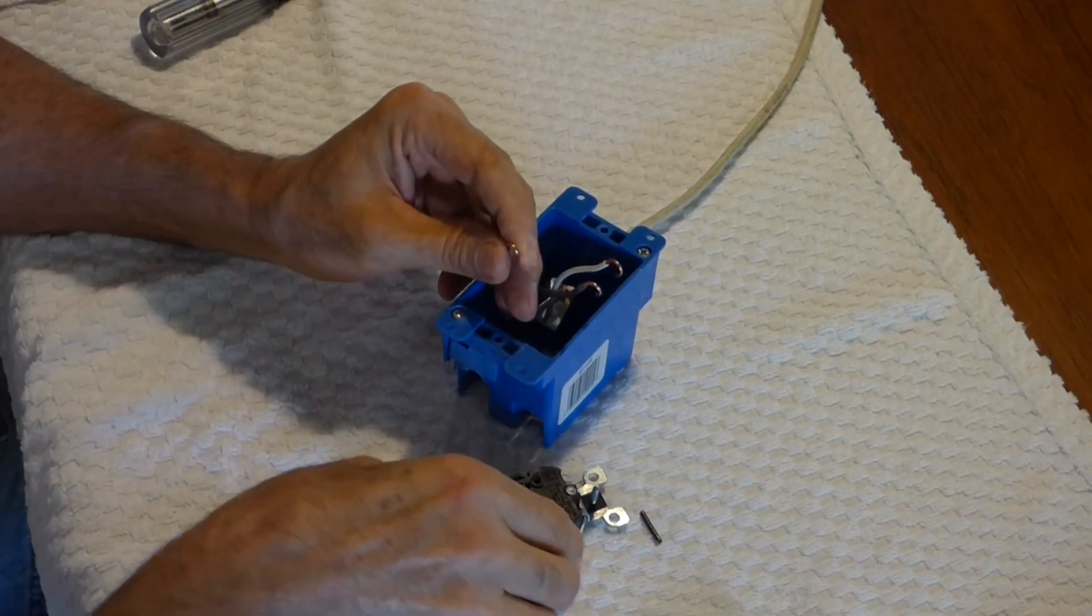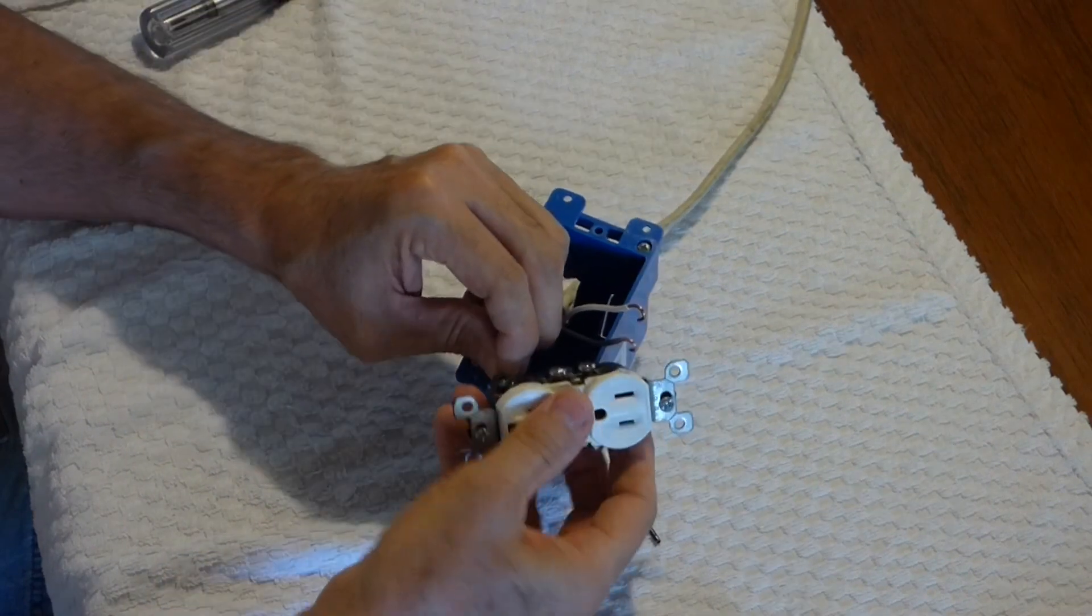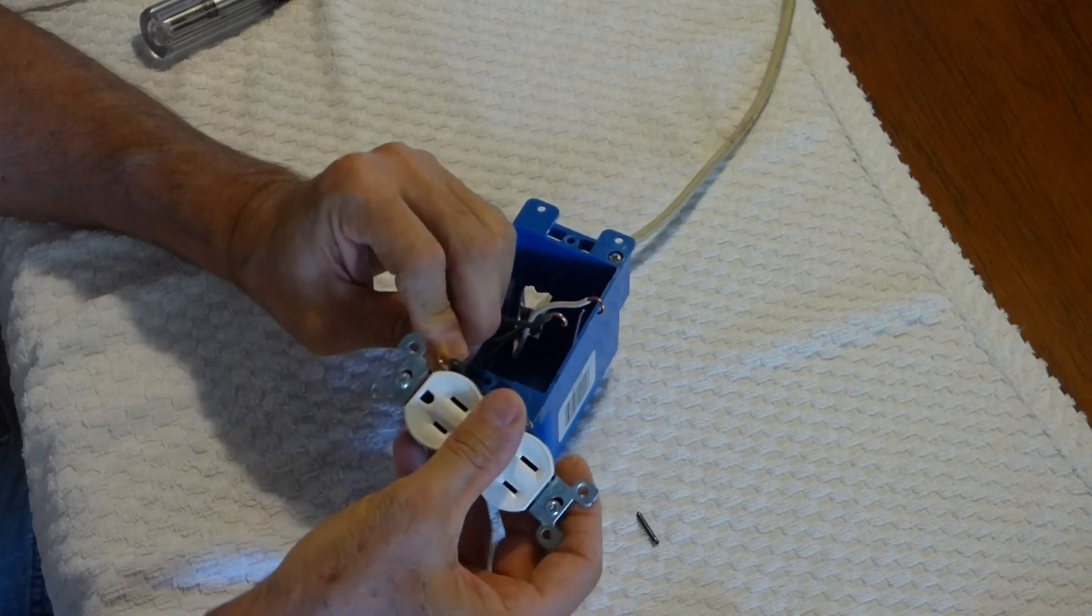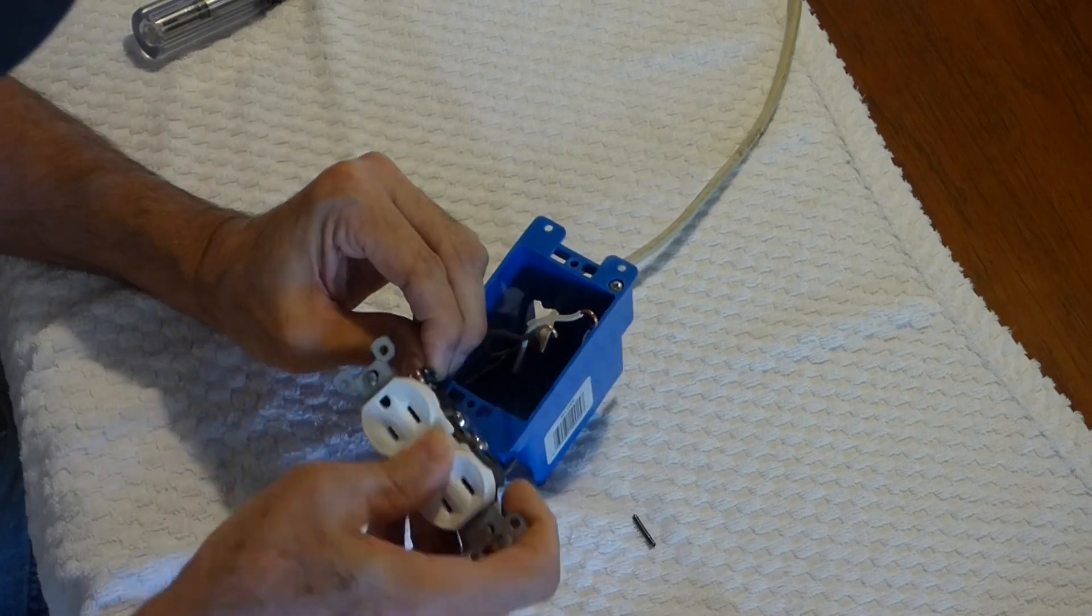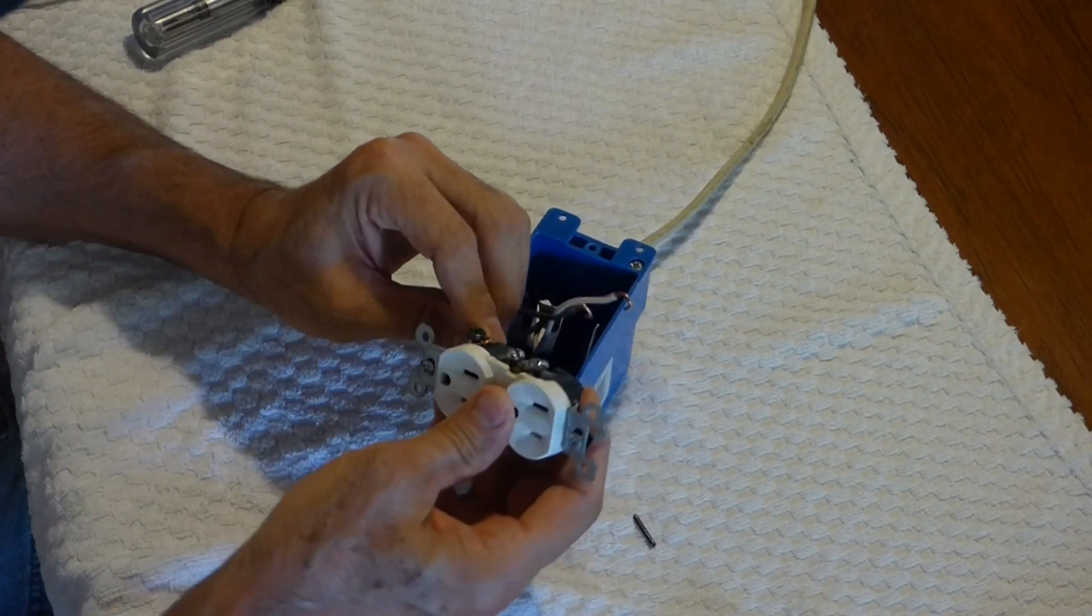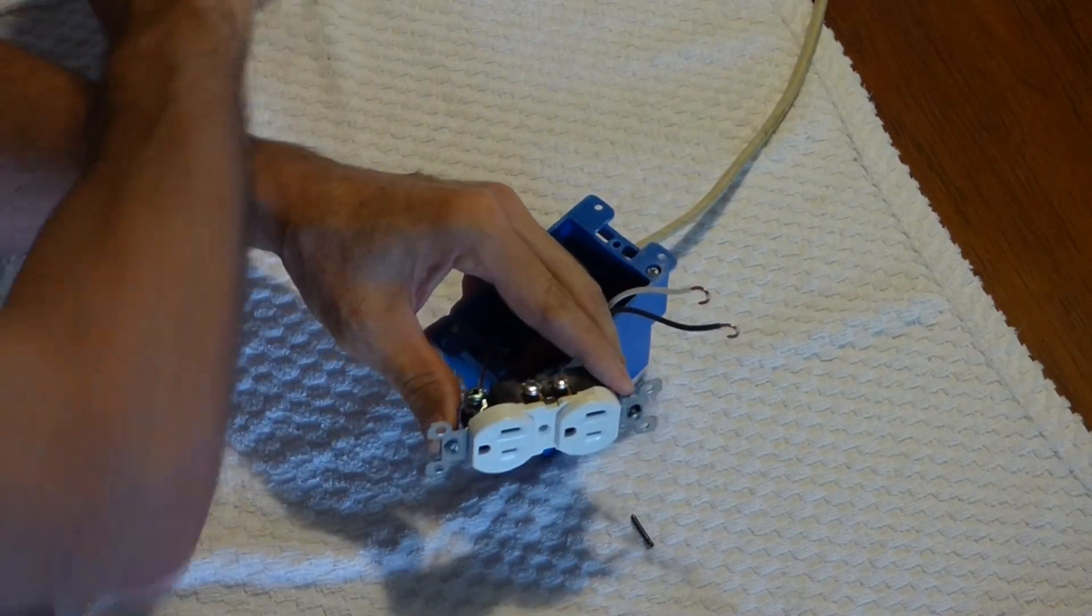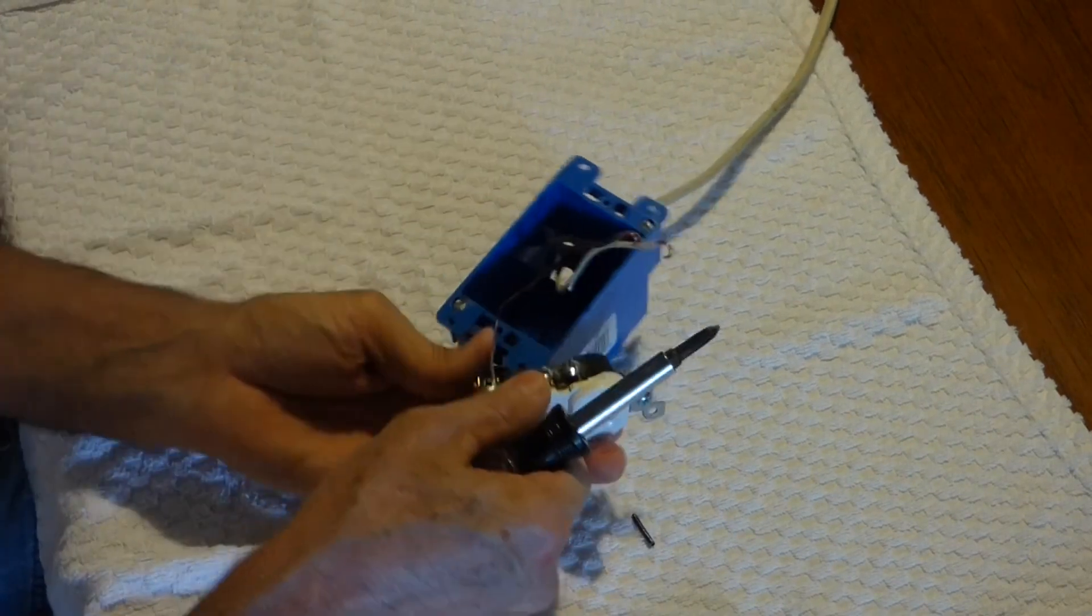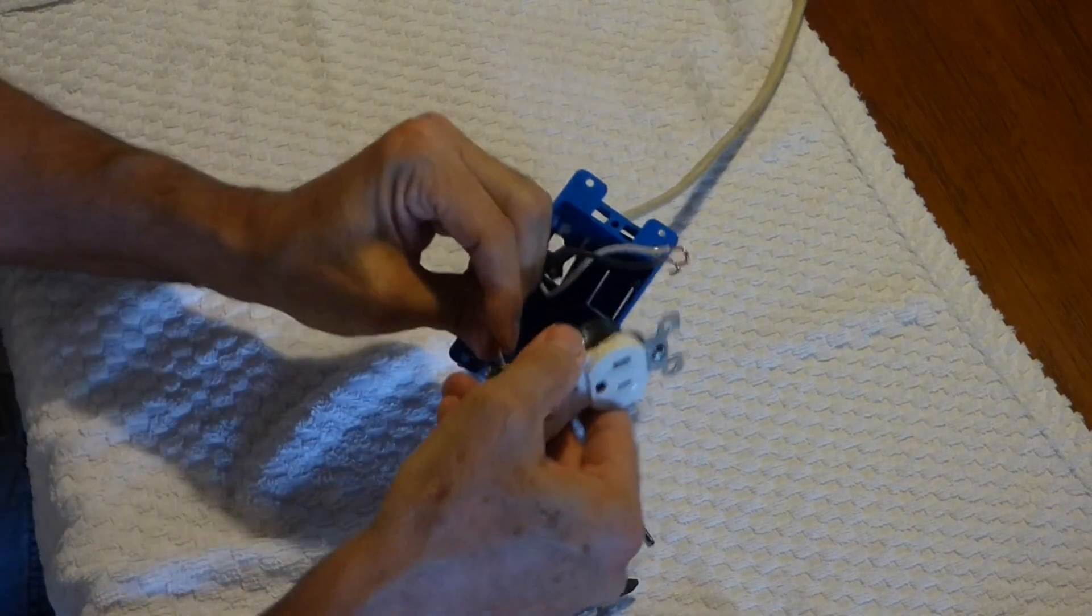Now with that done, I hook up the ground wire first. You don't want to put it on like this, because when you tighten, it's going to have a tendency to want to push that wire out. So you make the shepherd's hook or the J hook in the same direction that you'll be tightening the screw. Just set that on there, take your screwdriver, tighten that down, and you want to make sure you're good and snug. Double check that.